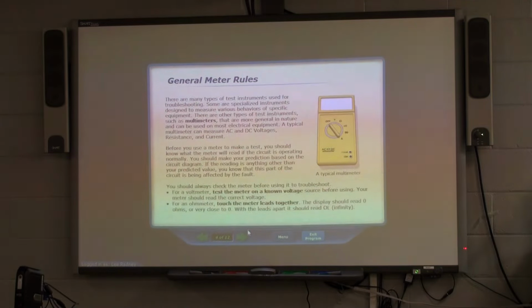General meter rules: always check the meter before it's used for troubleshooting. For a voltmeter test, check the meter on a known voltage. This is very important. Meters can go bad. The best way to make sure your meter is good is to go to a known voltage. If you're going to measure AC, go over to a socket. When you measure 115 or 120 volts on that socket, you know your meter's functioning. But God forbid you go over to a 480 circuit with a bad meter lead, read 0 volts and go, it's okay, no power here, and start turning the screws on that thing. So you first want to make sure you've got a meter that is functioning, and then go measure and make sure you've got a dead circuit.